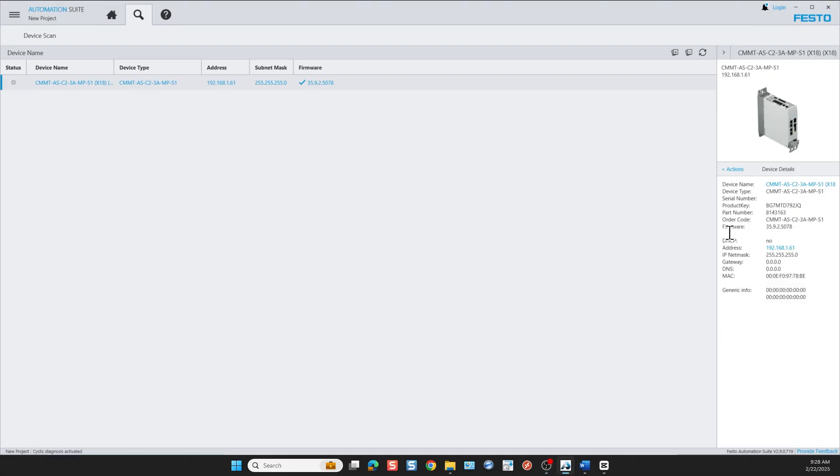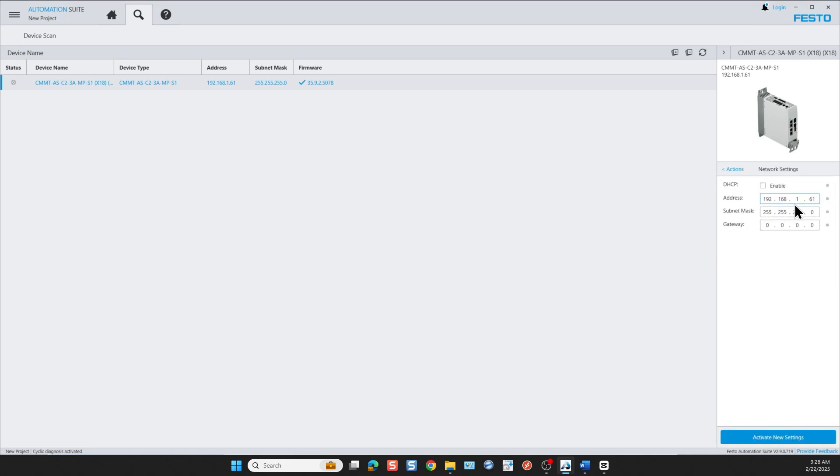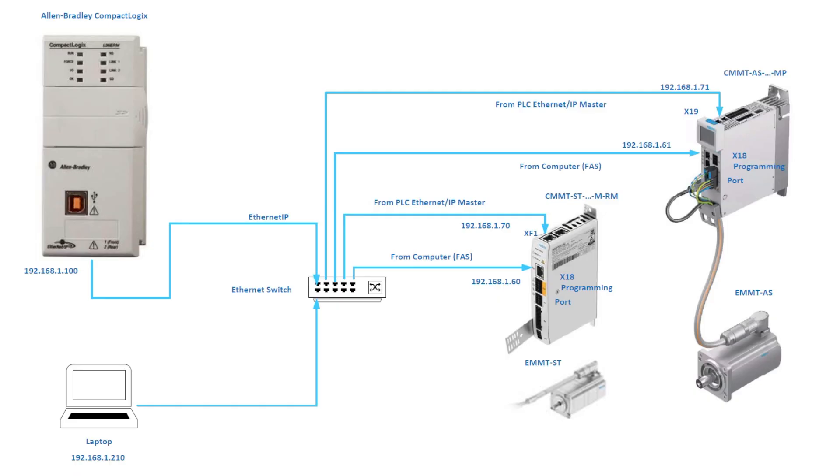Let's go back and click on actions and we go to network settings. Here we can modify the IP address. Automation Suite is able to find the device through DHCP on first startup, so you would turn off the DHCP enable and you would assign an IP address to the device along with the gateway. What this does is it sets the front X18 port IP address, not the top port.